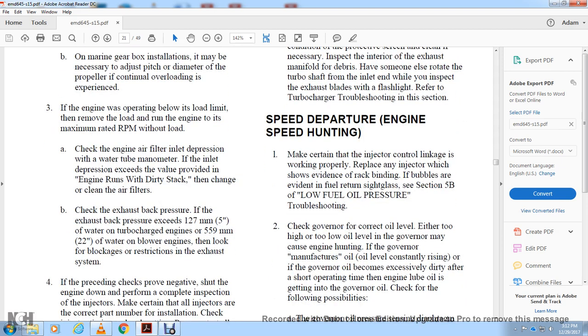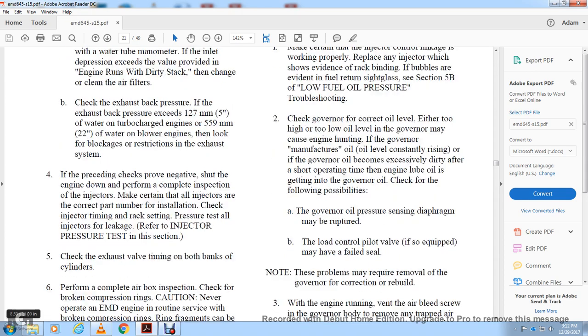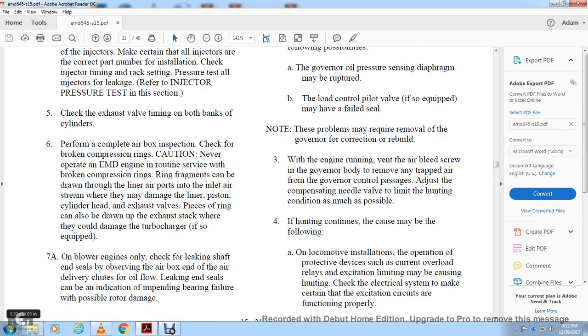If all preceding checks prove negative, shut the engine down and perform a complete inspection. Check injector timing and rack settings, pressure test all injectors for leakage, and refer to the injector pressure test section. Check cylinder exhaust valve timing on both banks. Perform a complete airbox inspection and check for broken compression rings. Caution: never operate an EMD engine in routine service with broken compression rings; ring fragments can be drawn through the liner into the inlet air ports and air stream, which could cause damage to the liner and piston.